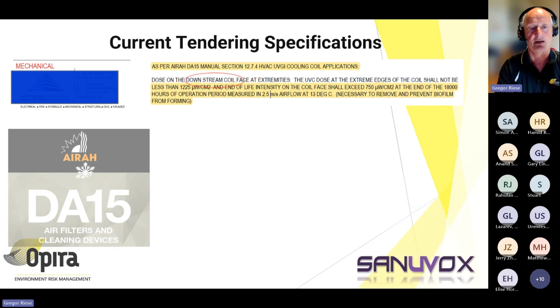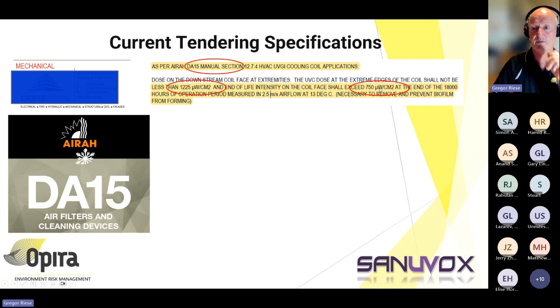This particular one, I've just blotted out the company. It's not important. A whole lot of businesses, consulting engineers are using DA15 as their source, and DA15, it's a wonderful document. It's an AIRAH published document. If you want to know about filters, it's fantastic. It also has a small section on UV at the back, and this particular specification says, look, we want 1225 microwatts per centimetre squared at the beginning of life, and at the end of life, you will have 750 microwatts at the end of 18,000 hours, which is around 2 years.